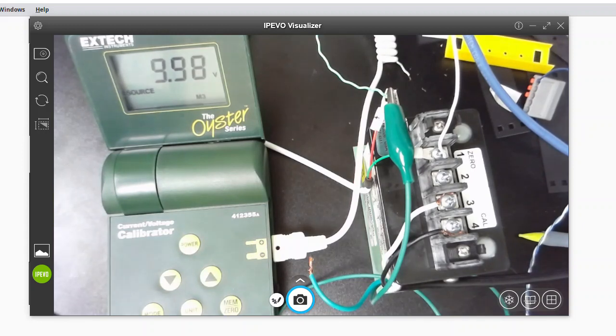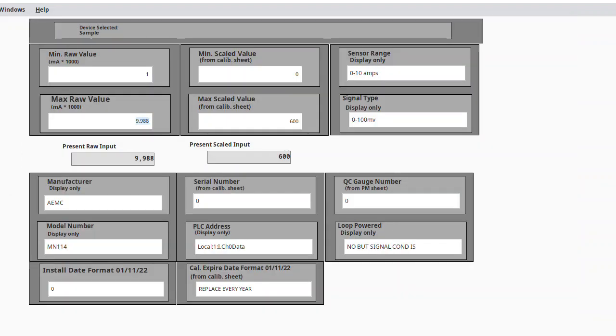Now that I'm injecting the correct high signal, I'm going to go back to my calibration application. We can see what we got here. It says that my present raw input is 9.98987 volts, which is what I'm injecting in there. You're never going to get exact. It's always going to float a little bit. But we're pretty close. So I'm going to take this number here and type it in over there. That becomes our max. We already set the scaled min and max earlier from our spec sheet. So now that we've set that, we should be reading 600 volts.